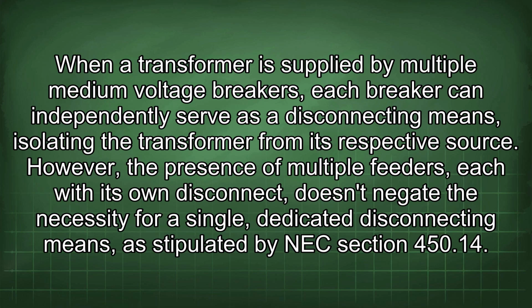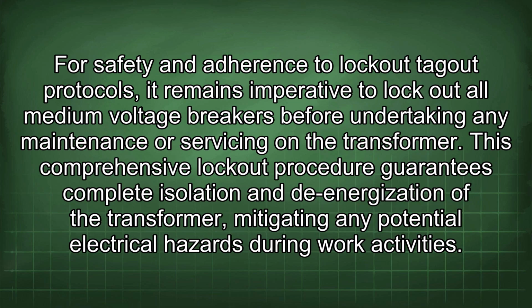However, the presence of multiple feeders, each with its own disconnect, doesn't negate the necessity for a single, dedicated disconnecting means, as stipulated by NEC Section 450.14. For safety and adherence to lockout-tagout protocols, it remains imperative to lock out all medium voltage breakers before undertaking any maintenance or servicing on the transformer. This comprehensive lockout procedure guarantees complete isolation and de-energization of the transformer, mitigating any potential electrical hazards during work activities.